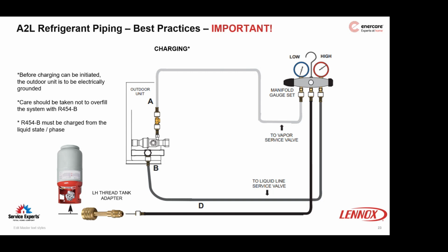Notice the left-hand thread charging adapter that is likely to be required for these refrigerant tanks. I've recently heard that the R454B tanks may actually come equipped with them, but nobody's actually proven that the tank comes with the adapter. You may require these left-hand thread adapters to get onto these new tanks, any of the A2L tanks, and it's just a protection device so that we don't cross-contaminate.